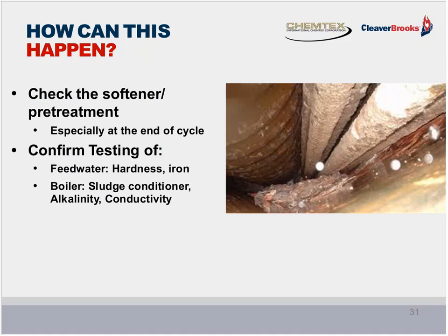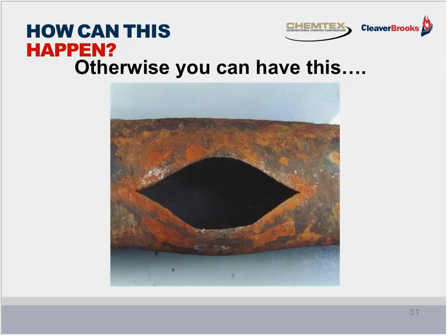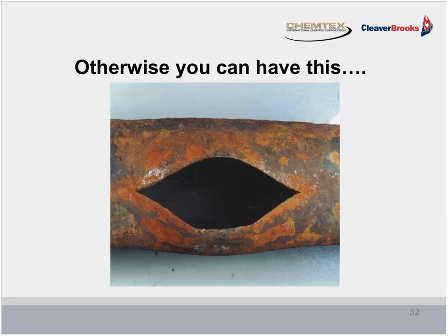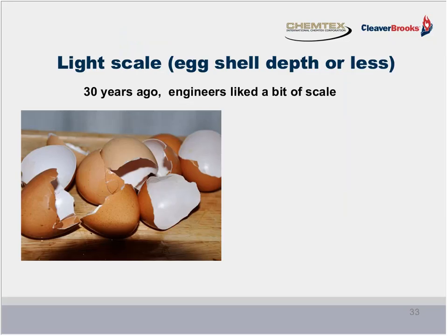And the last part of this testing aspect of it is make sure your testing reagents are good. Are your test results matching those of your water treatment supplier that comes into your facility on a regular basis? Because if you open your boiler up and it's got scale in it, there's a possibility you can have a tube burst, a tube failure. It can result in downtime and costly repairs, which Steve alluded to before.